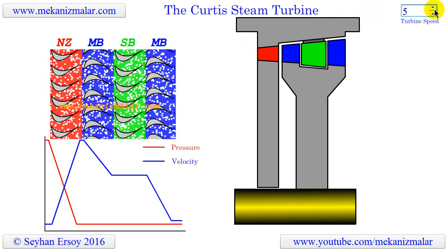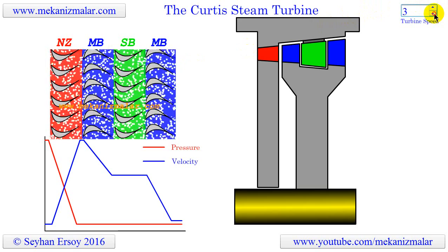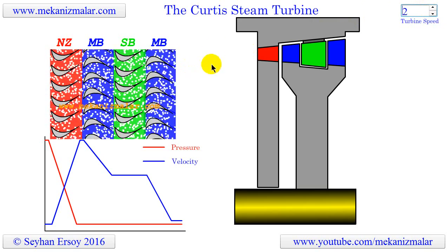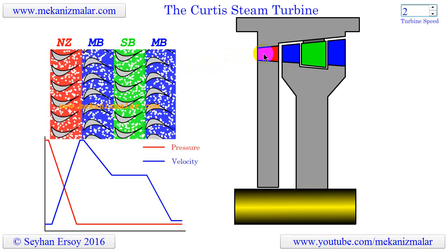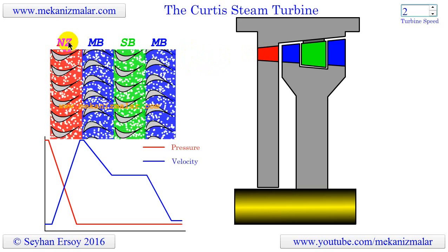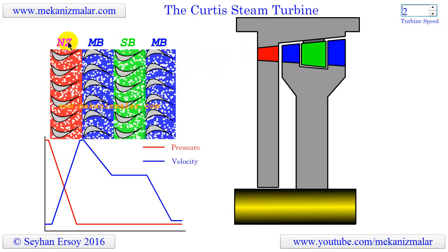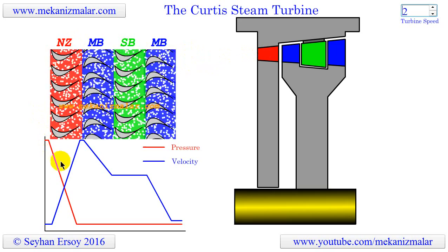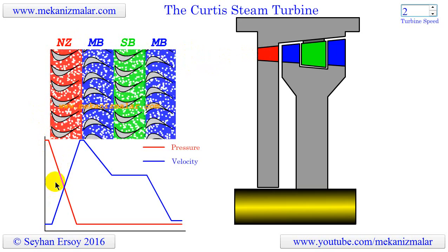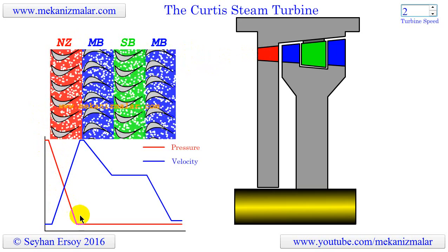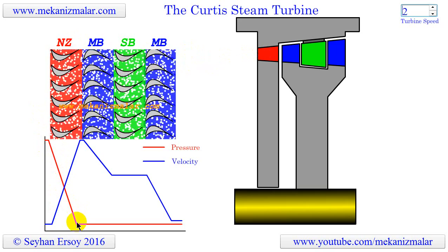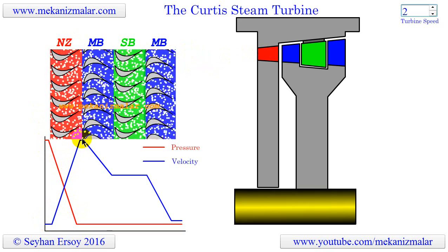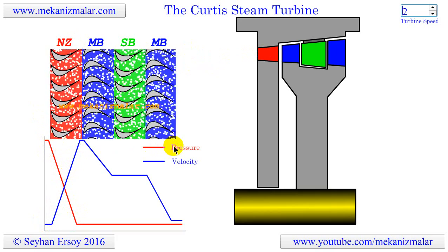The first stage, shown in red, is where the nozzles are located, indicated by the characters NZ. Here, the steam's potential energy is converted to kinetic energy. As you can see in the plot, this stage corresponds to a substantial pressure drop, which in turn increases the velocity of the steam proportionally.